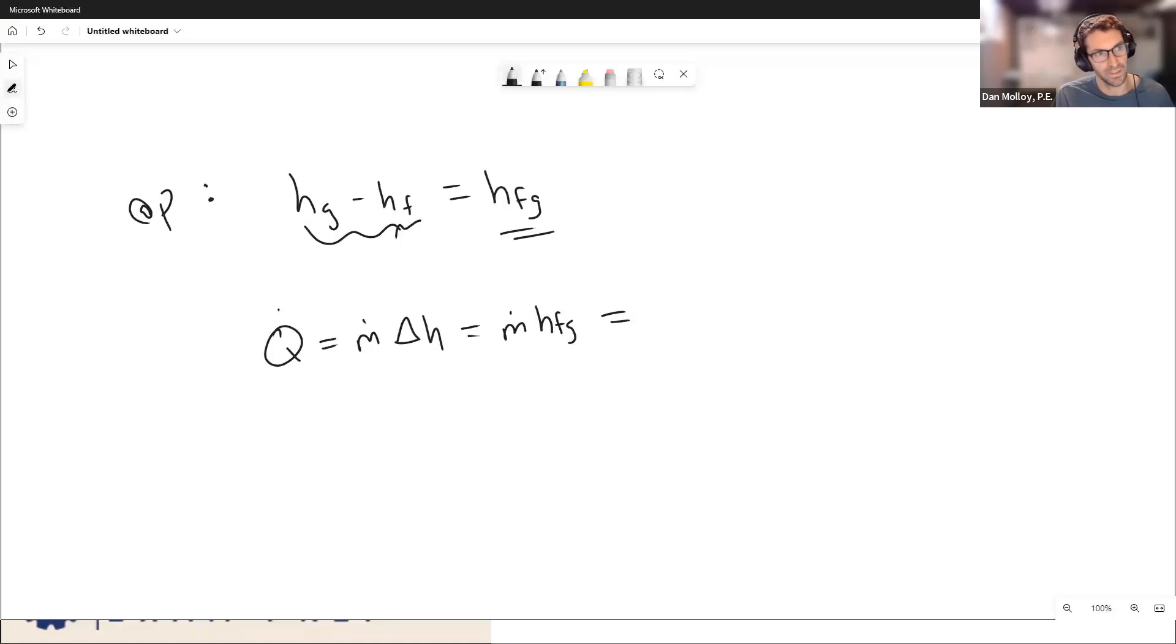And then the other side, it's just how much heat does that add to the water. And we use a rule of thumb there, 500 GPM delta T.